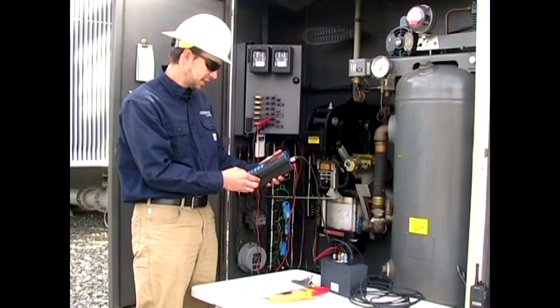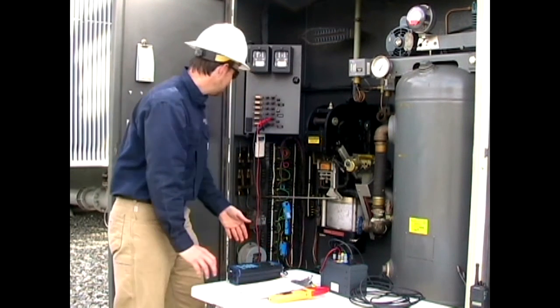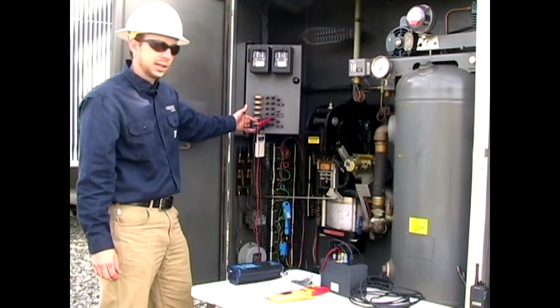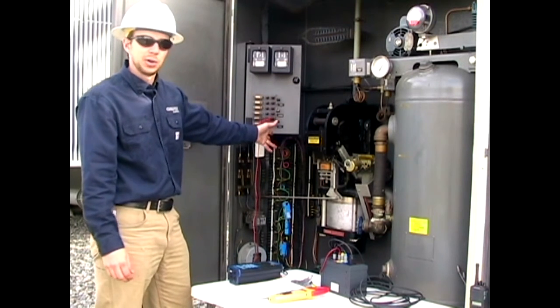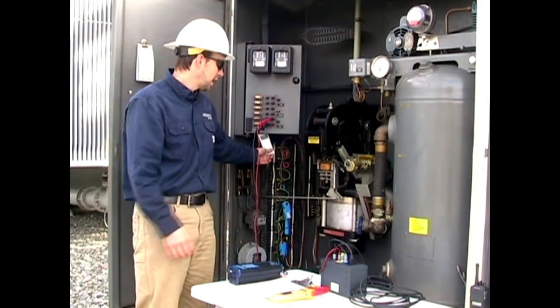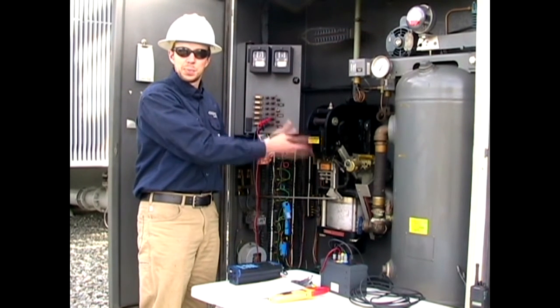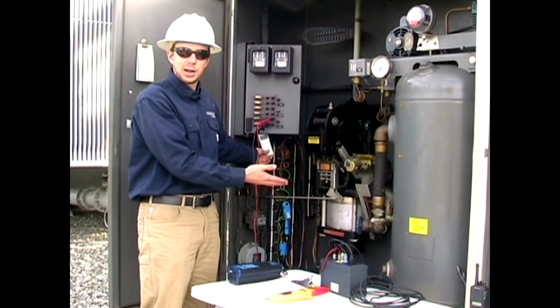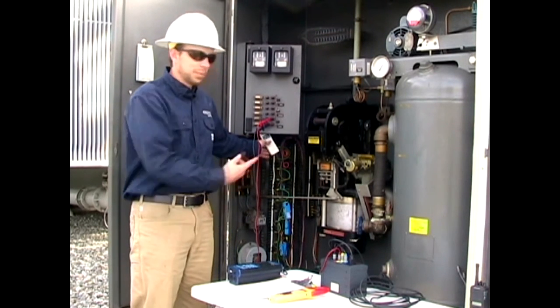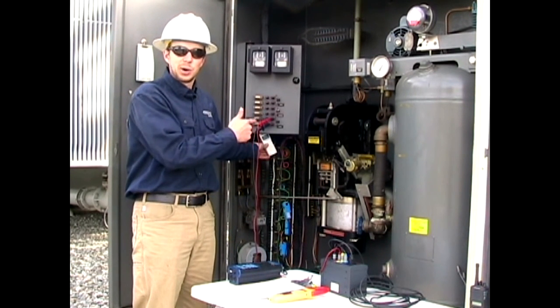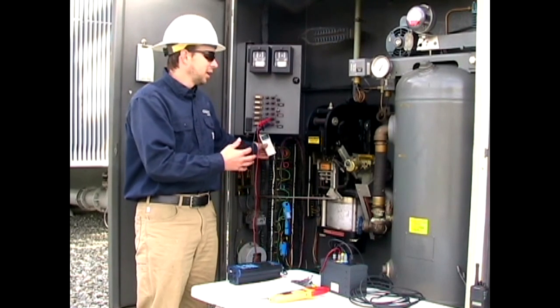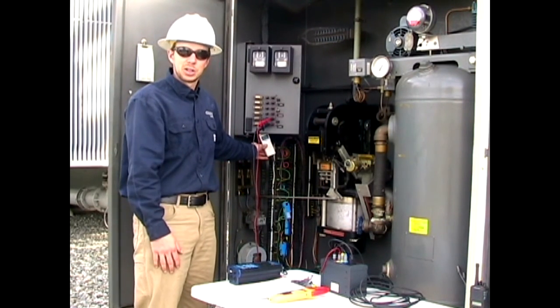We've saved this test. Next, you keep your DC supply on the same, but you'll move your amp probe to the line that will go to your close coil, and you'll catch a close on it, and then you'll want to move this back and catch another trip. Usually you want 2 or 3 trips and 2 or 3 closes so you can overlay them and make a true evaluation.